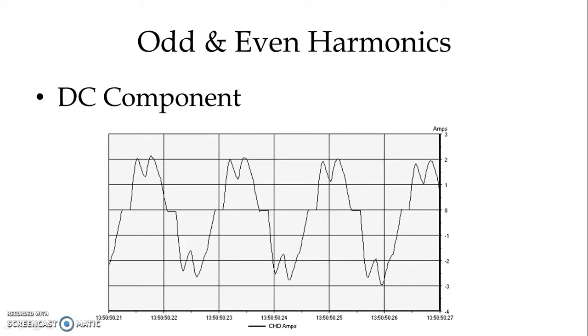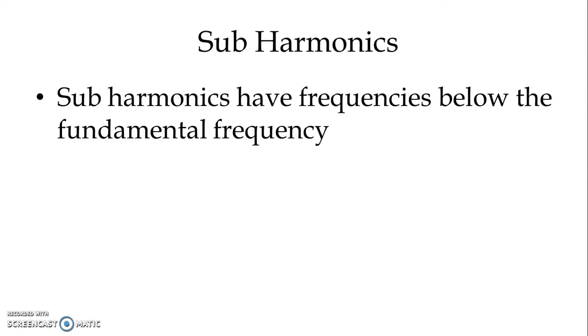We usually look at harmonics as integer numbers, but some applications produce harmonics that are not integers. Electric arc furnaces and arc welders are examples of loads that generate non-integer harmonics. But in both cases, once the arc stabilizes the non-integer harmonics mostly disappear, leaving only the integer harmonics. Sub-harmonics have frequencies below the fundamental frequency, and they may arise due to resonance between harmonic currents or voltages with the power system capacitance and inductance.